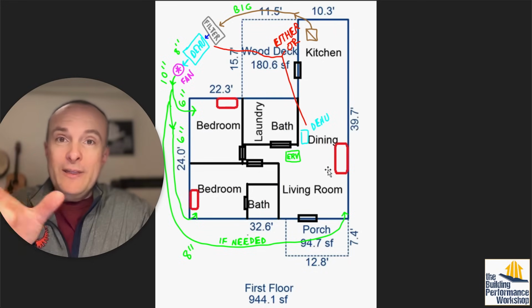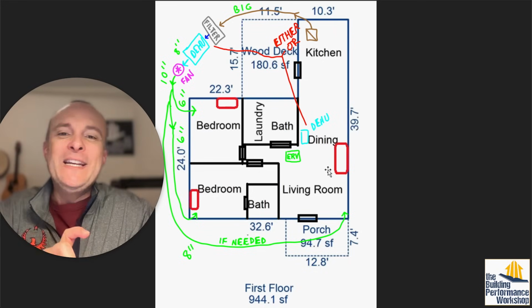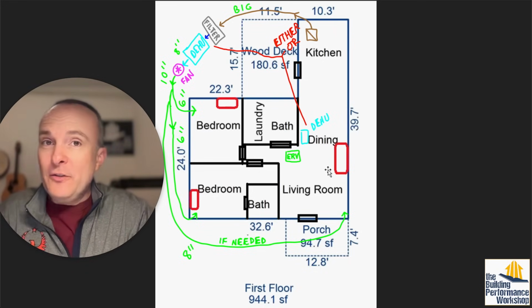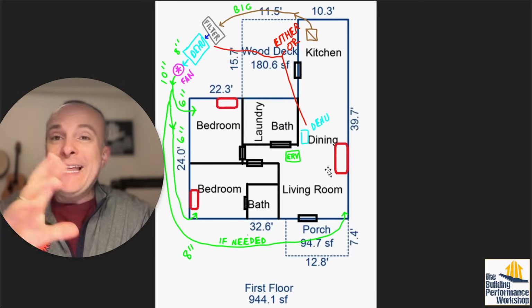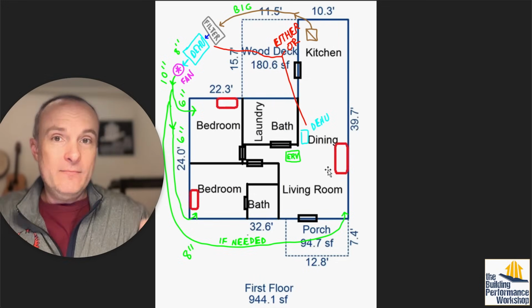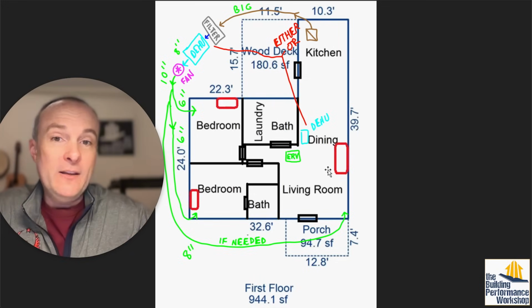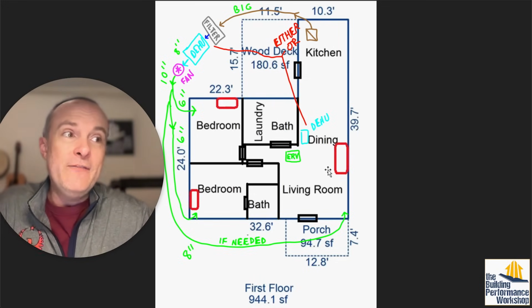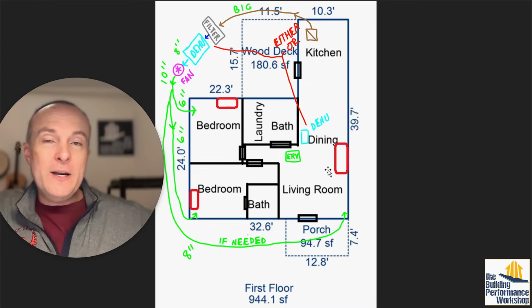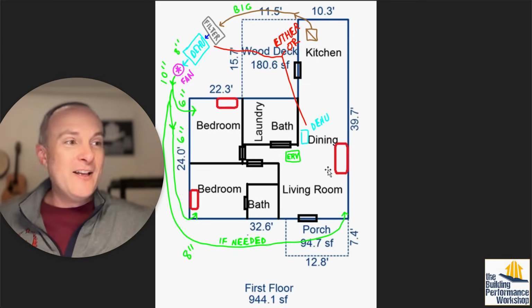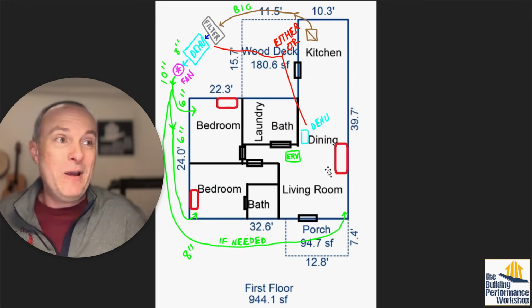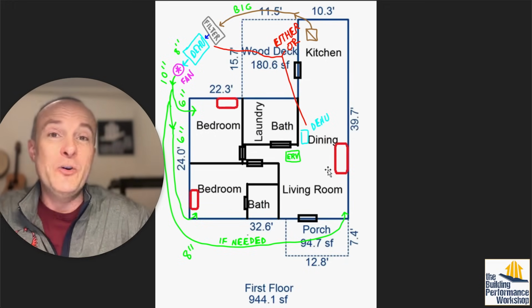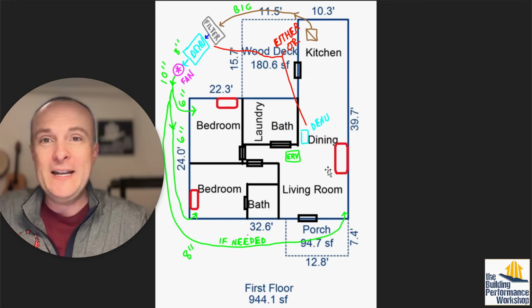And you wanted to make sure that you can dial it down too. So if we didn't need the full 300 CFM, which is likely going to be around his 1 air change per hour rate, then we don't have to do that, because maybe he found that just 1 window open in one end of the house, 1 window open in the other end of the house with 1 fan does plenty, and maybe that's only 75 CFM. So a quarter of what a 300 CFM fan can deliver.